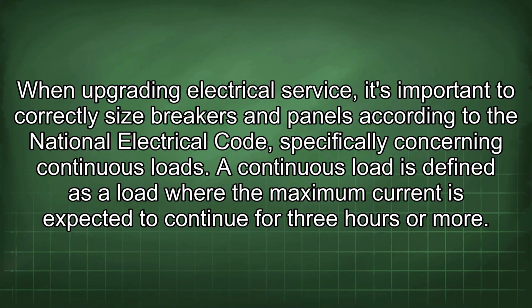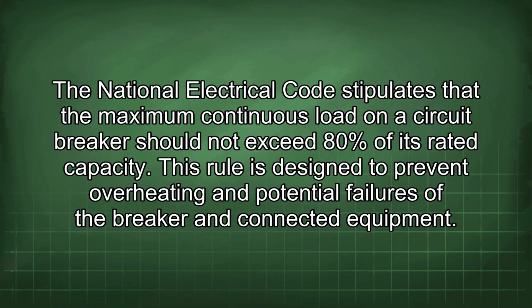When upgrading electrical service, it's important to correctly size breakers and panels according to the National Electrical Code, specifically concerning continuous loads. A continuous load is defined as a load where the maximum current is expected to continue for 3 hours or more. The National Electrical Code stipulates that the maximum continuous load on a circuit breaker should not exceed 80% of its rated capacity. This rule is designed to prevent overheating and potential failures of the breaker and connected equipment.